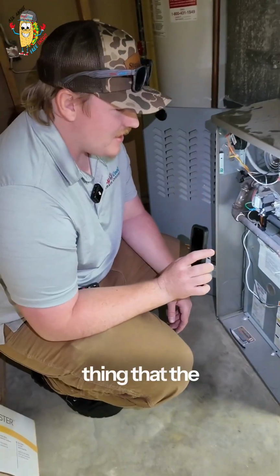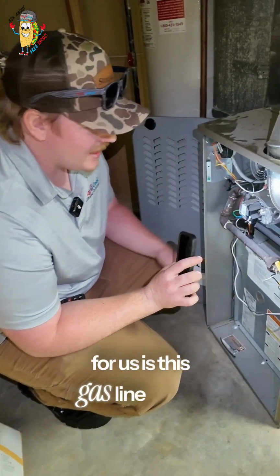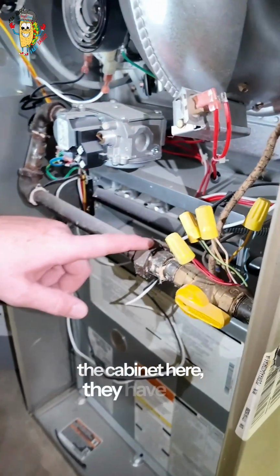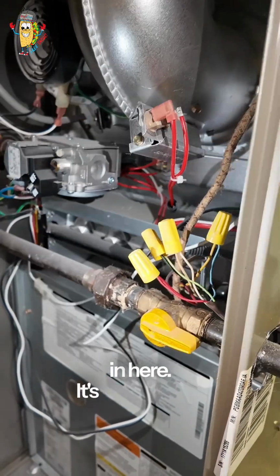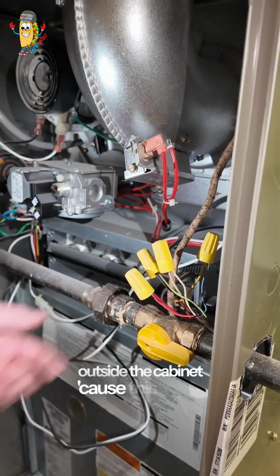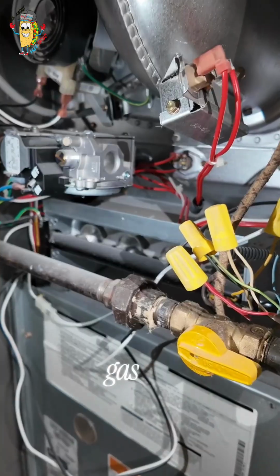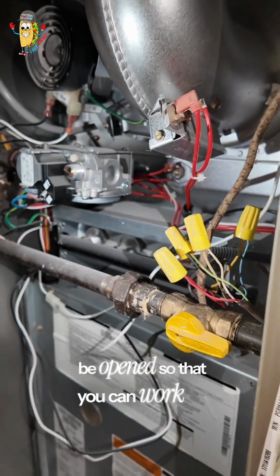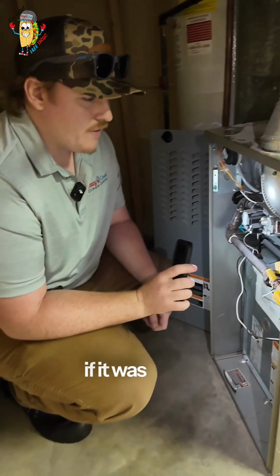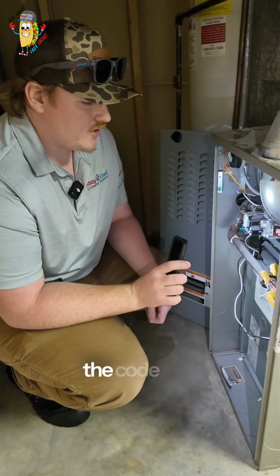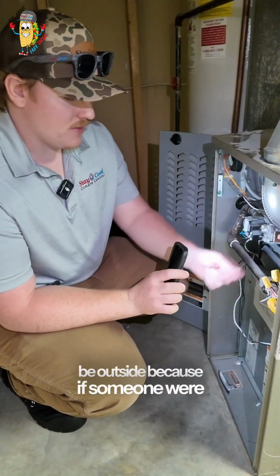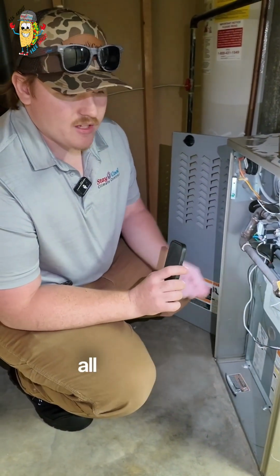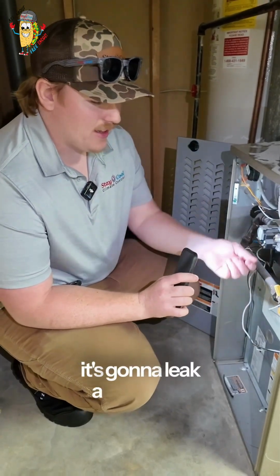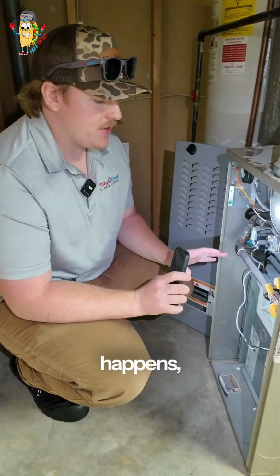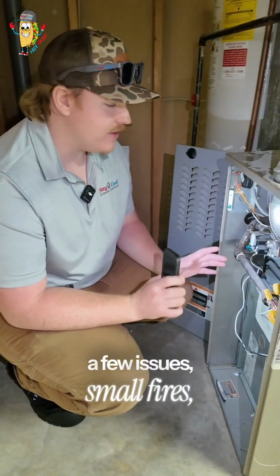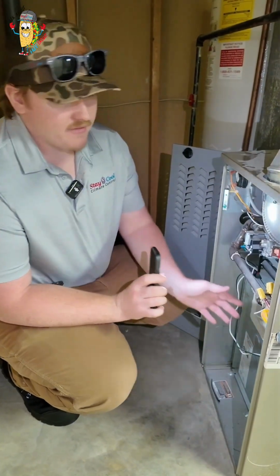And so another thing that the inspector highlighted for us is this gas line for the furnace. You can see inside the cabinet here, they have the union and the shutoff both in here. It's not allowed, it's got to be outside the cabinet because this union is an unsealed section of the gas line. It's there to be opened so that you can work on the gas line. And back in the day, they didn't care if it was in the cabinet, but recently they changed the code that requires it to be outside, because if someone were to open this union and then not close it up all the way, leave it cracked, it's going to leak a little bit of gas, and this is right where combustion happens. So it can cause a few issues, small fires, things like that. So, to prevent that, it's got to be outside the cabinet.